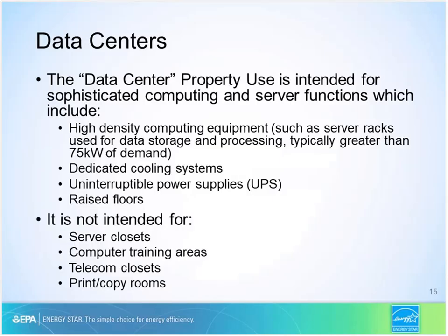We see a lot of data centers benchmarked within offices, so we want to cover this specific property type. For true data centers, make sure the space complies with the EPA definition. The space should be broken out as a data center if any of these conditions are met: the space has a constant demand load of more than 75 kilowatts, there is a dedicated cooling system, there is an uninterruptible power supply (UPS), or there are raised floors. The data center definition should not be applied to small server closets, computer training areas, telecom closets, or print and copy rooms — those should be included as part of the primary property type, typically the office.